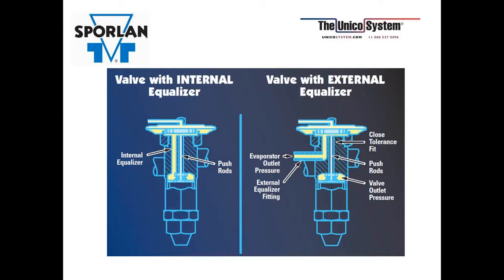Unico uses only the external equalized version. You can never go wrong with using an external equalized TEV, but there are two circumstances where you must use the external equalized version. One is an AC application, AC or heat pump, and the other is whenever a refrigerant distributor is being used.